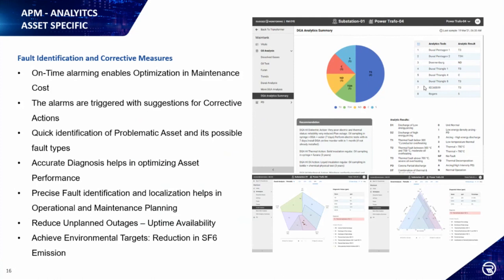So those alarms need to be taken seriously, but at the same time the action needs to be planned. The need for the action is planning; we need to plan ahead for that particular failure. That's where we need a change in philosophy of alarm management, between alarms from a SCADA system versus alarms from a monitoring or APM system.